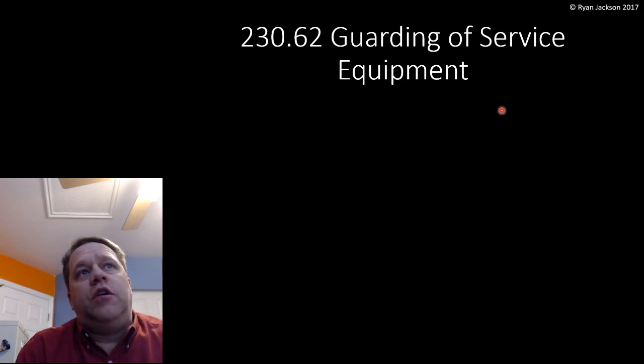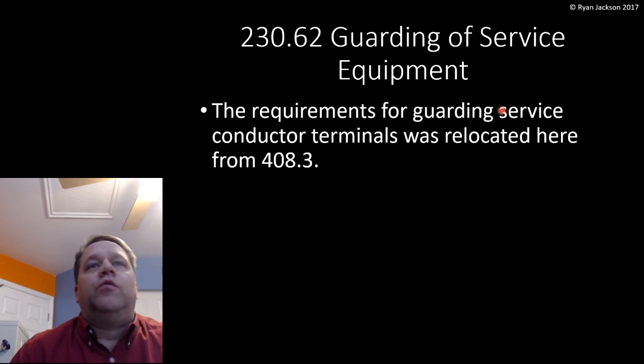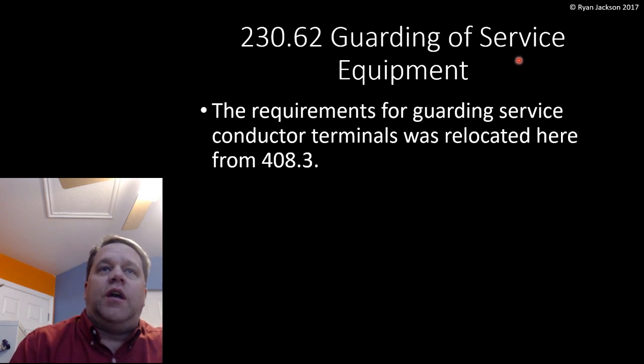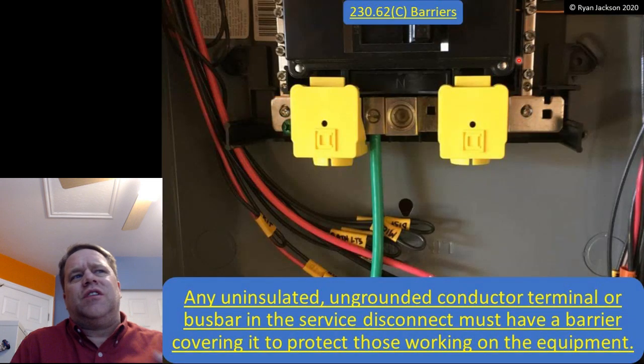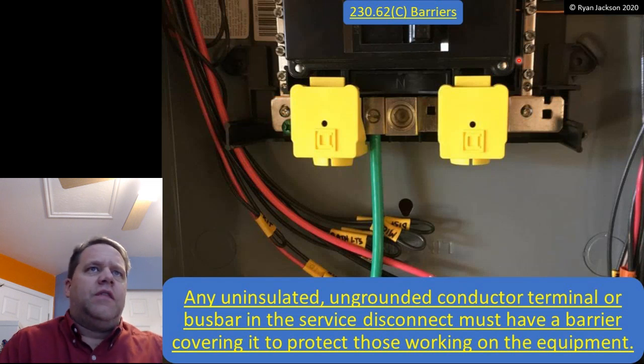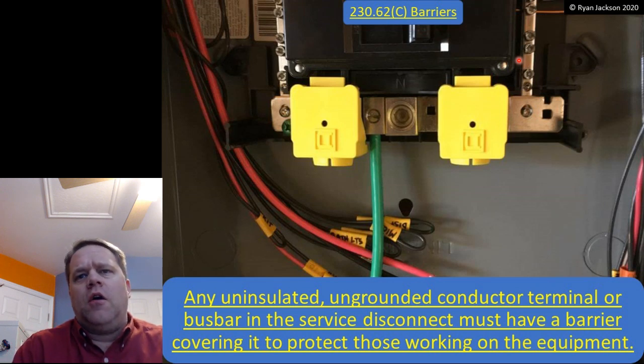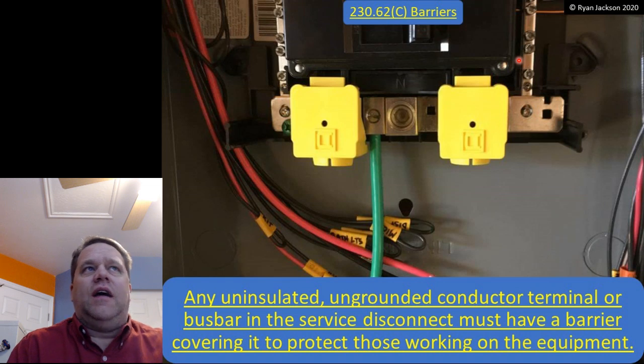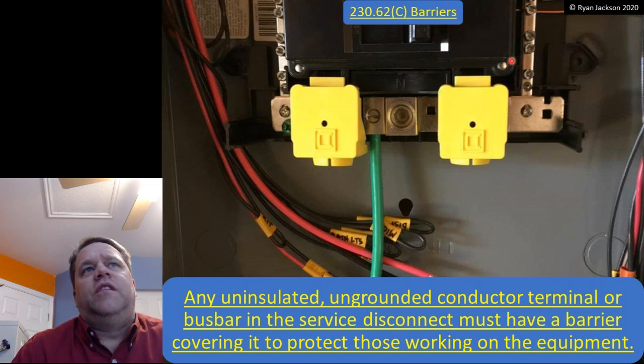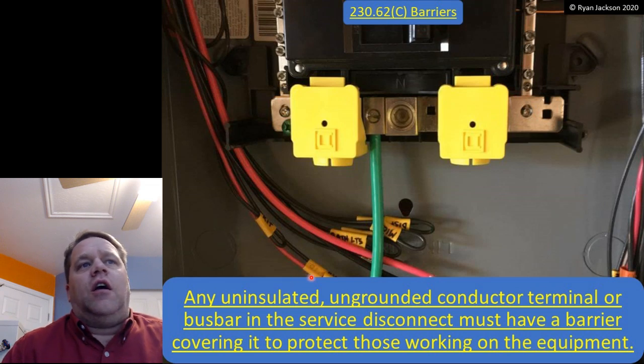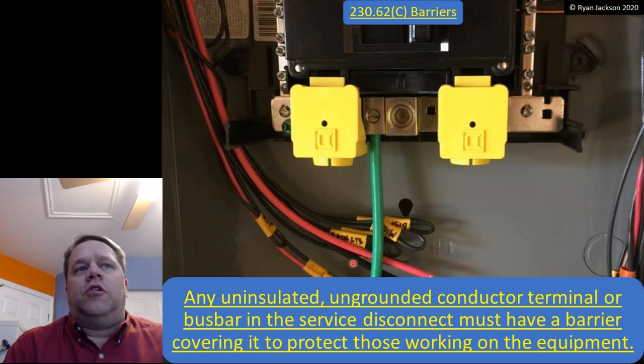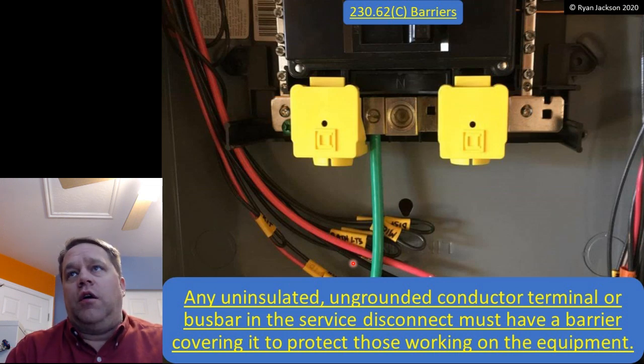The next change is in 230.62, guarding of service equipment. The rules for guarding service conductor terminals were relocated here from 408.3. This really isn't a change per se. They just moved this from Article 408 over to Article 230, which is probably appropriate. Article 408 covers panel boards, and Article 230 covers services. Well, this is unique to services, so it probably should be in Article 230. So 230.62(C) says that any uninsulated, ungrounded conductor terminal or bus bar in the service disconnect must have a barrier covering it to protect those that are working on the equipment.